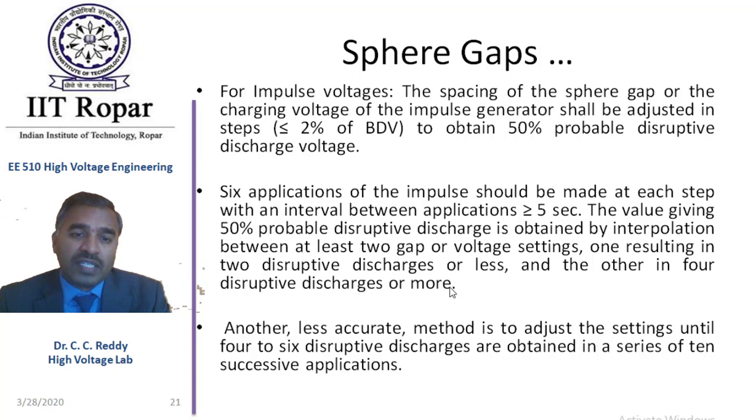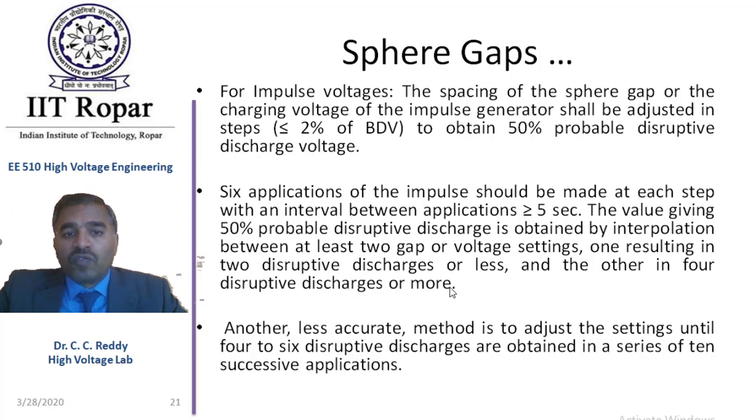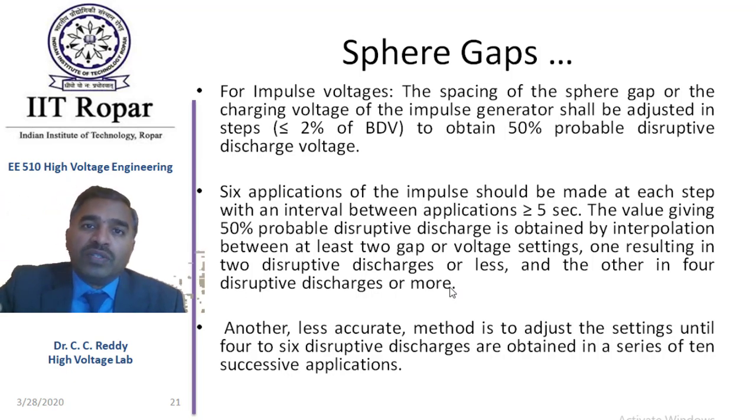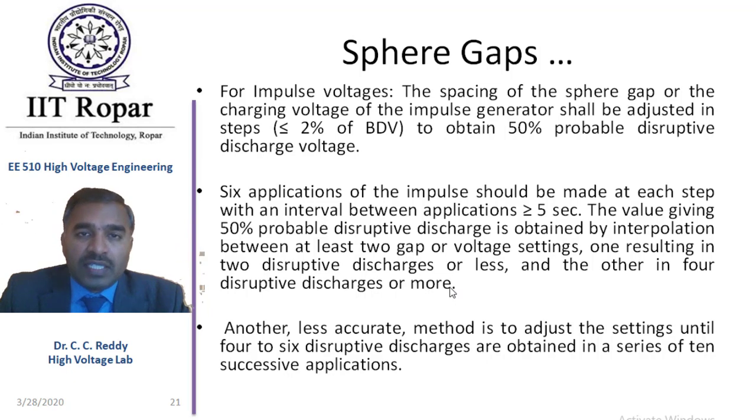See, one resulting in 2 disruptive discharges or less, the other 4 disruptive discharges or more. Or, in other words, one should have the 2 steps between which you will interpolate. So, we will be applying the voltages in steps, right? At each step, 6 times we are applying.